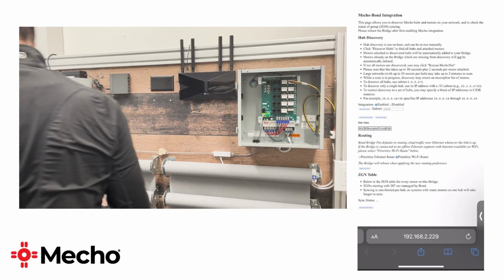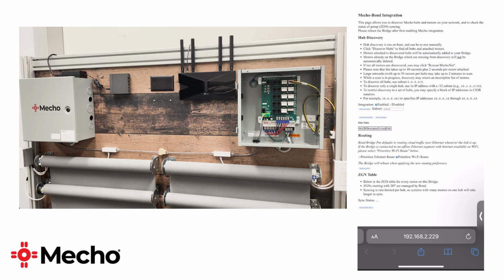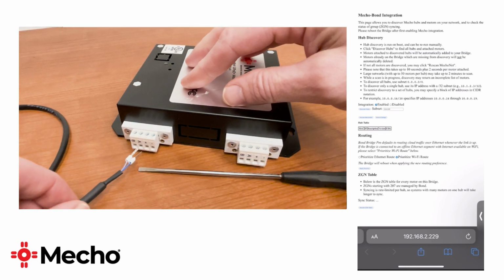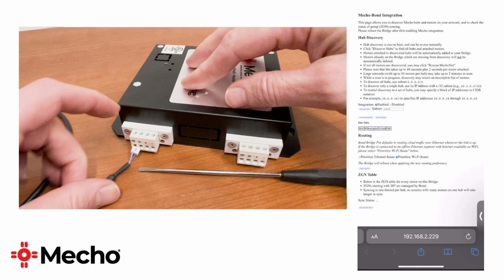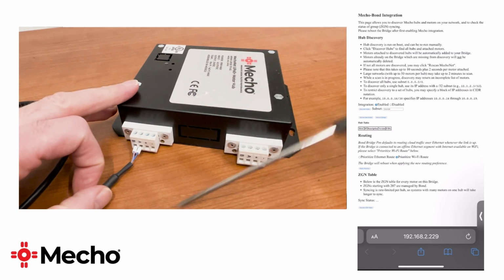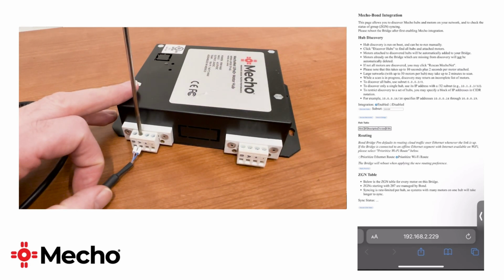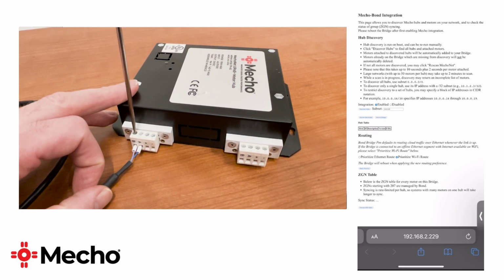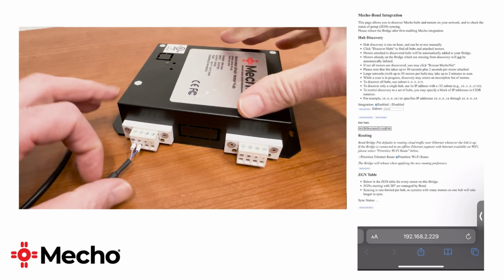I first mount and power up the PoE switch using the supplied power adapter. I then mount and power up the IP router. I make the connections for the MechoNet specialty cable supplied in the kit in the accessories bag to one of the 4-pin terminal blocks on the Mecho motor hub. Insert the ferruled ends of the cable into the two MechoNet ports labeled A and B. The blue wire goes to A and the blue and white wire goes to B. Using a small flat blade technician screwdriver, tighten down the screws to secure the cable in the terminal blocks, being sure not to over-tighten them.